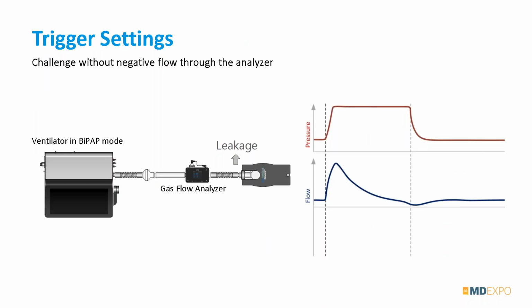And as we have learned earlier, the default trigger settings on gas flow analyzers are typically based on exactly that to happen, that the flow goes negative. Otherwise, they don't work anymore. So in such a BiPAP ventilator test situation, the flow waveform cannot really be used sufficiently to trigger anymore. So if you have an analyzer on the default trigger settings and you measure such a situation, then it's not going to measure a rate, for example, or tidal volumes and stuff like that. So here we have to think about what else can we do, right? So take a look at the pressure waveform. Does this pressure waveform look like a good signal to trigger based on what we discussed earlier?